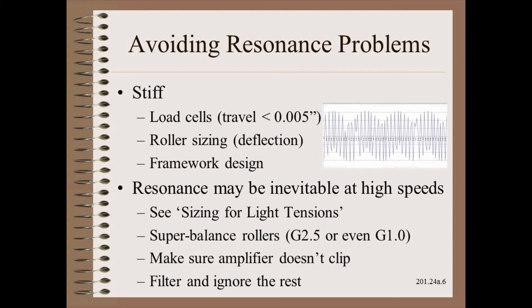Next, we use all of our best practices to size for light tensions as described earlier. Whether you reach resonance or not, balancing to G2.5 or even super-balancing to G1.0 is a cost-effective way to reduce vibration. The electrical engineer has two final tasks: first, to make sure that none of the amplifiers ever clip during vibration or especially during resonance, otherwise the mean or average will be shifted. Finally, they should filter and just try to ignore the rest, as the driver will usually just ignore the high frequency component as well.